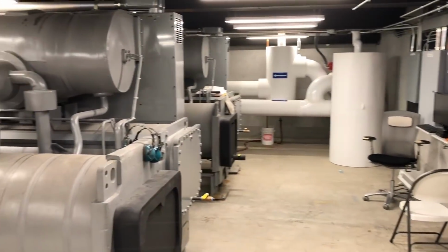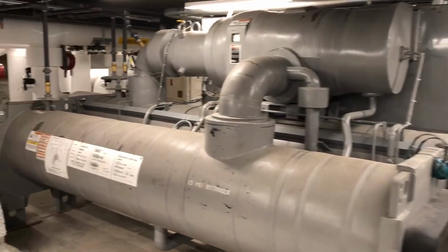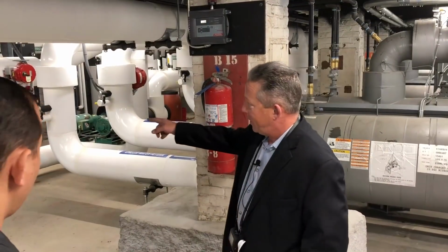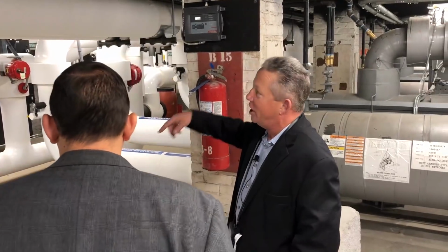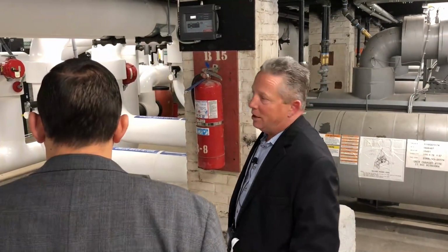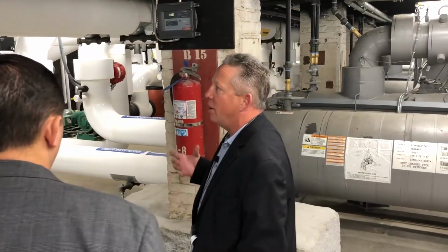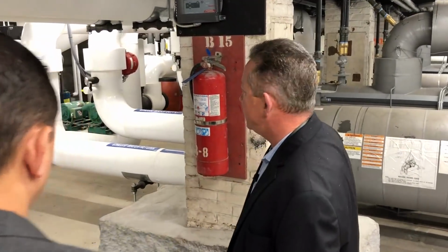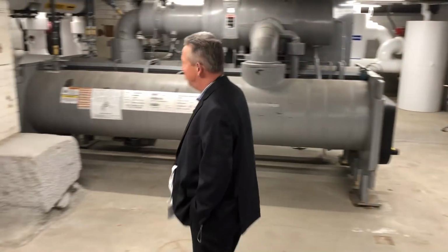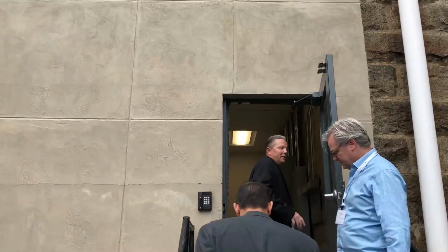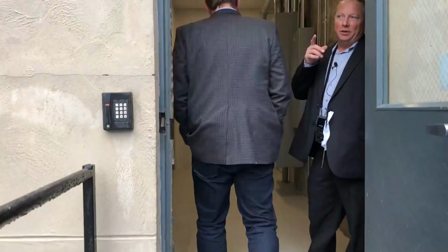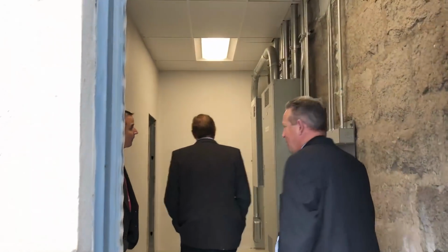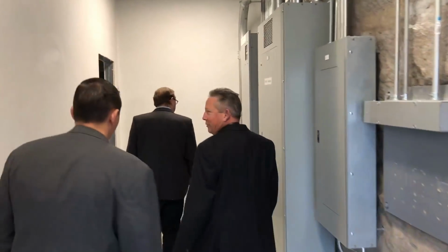So free cooling is literally circulating the glycol loop, the chilled water loop, interfacing it with the glycol loop at the heat exchanger, and then running it through fans and radiators outside. No moving parts other than fans and pumps. Makes it very efficient. And so that's the chiller room. There's about 900 feet just in 8-inch pipe, triple welded Schedule 80 steel pipe for that cooling tower loop. It's about 800 pounds for every 21-foot stick of pipe.